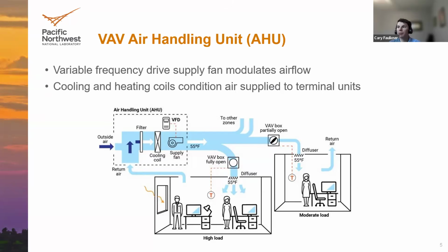The air will also typically be a mix of outdoor air and recirculated air that you condition before supplying to the terminal units, which I'll talk about on the next slide. But you can see downstream of the air handling unit, you supply that air, perhaps at a variable rate, but then you also have these VAV boxes that open and close to control the airflow to individual zones and condition those zones, potentially separate from each other, although what's happening upstream is going to be the same air. So, for example, the VAV box can open or close depending on the heating and cooling demands, or ventilation demands, from those individual zones.